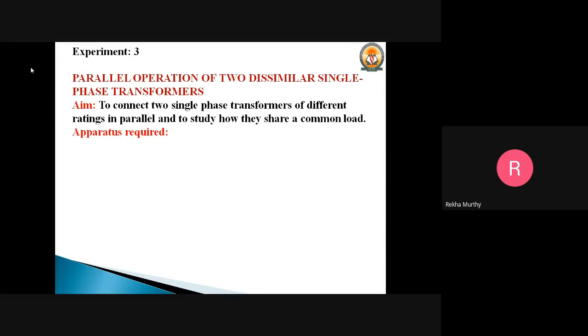So in this arrangement, what will happen? The primaries of the two or more transformers will be energized from the same source, and the secondaries will be connected to the supply with the same load. The following conditions need to be satisfied in order to avoid any local circulating current, and to ensure that the transformers share a common load in proportion to their kVA ratings.